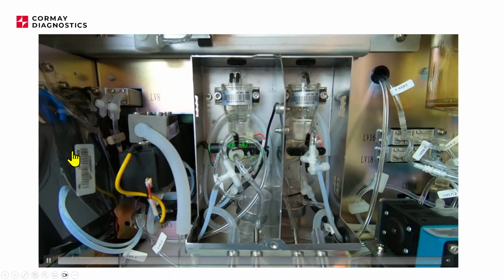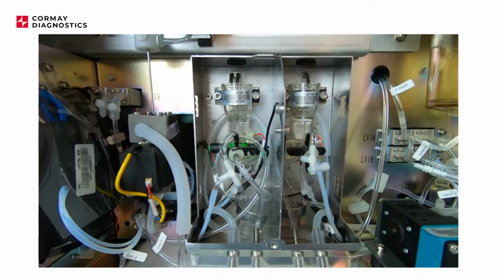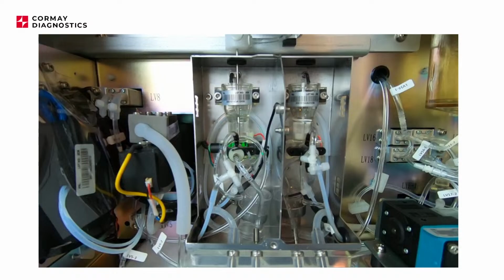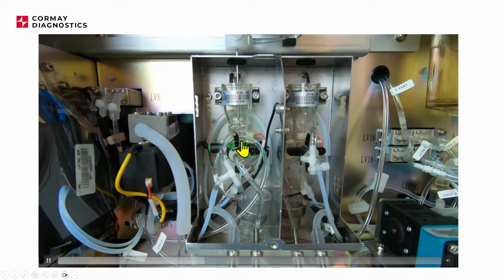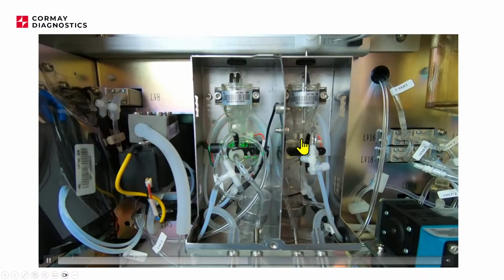Blood was aspirated, and as you can see, the rinsing head is above the CRP right now, going down into the CRP, dispensing like 10 microliters, and now it's going to the WBC. It's mixing. It's still outside cleaning. The liquid was removed. Now it's mixing with the diluent. Now it's going down. It's aspirating volume. It's going down to the RBC, and in the meantime, the analyzer already adds the lyse and mixes everything. So the lysing process happens here, and we have the second dilution here, and the reaction for CRP is also happening at the same time here in the chamber.